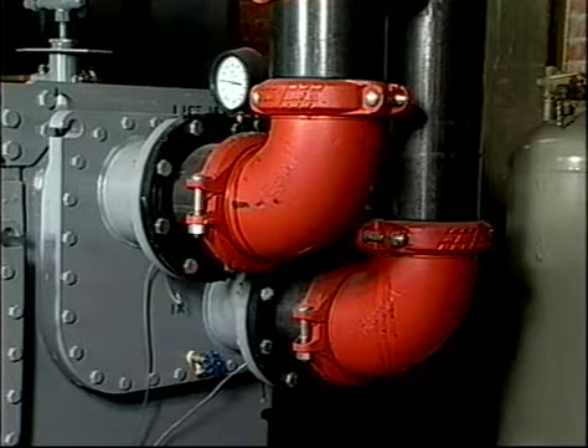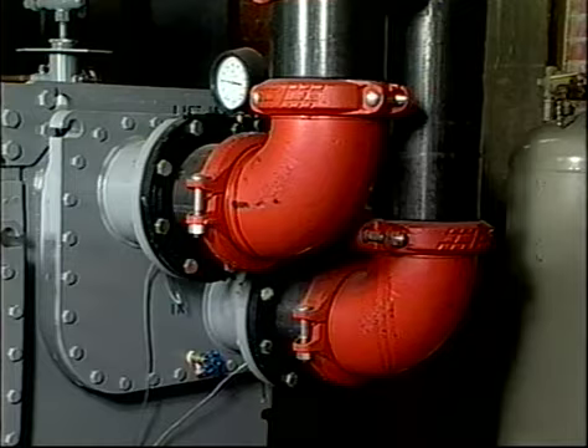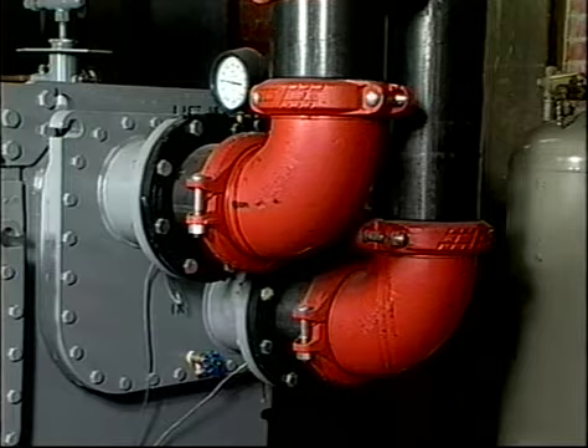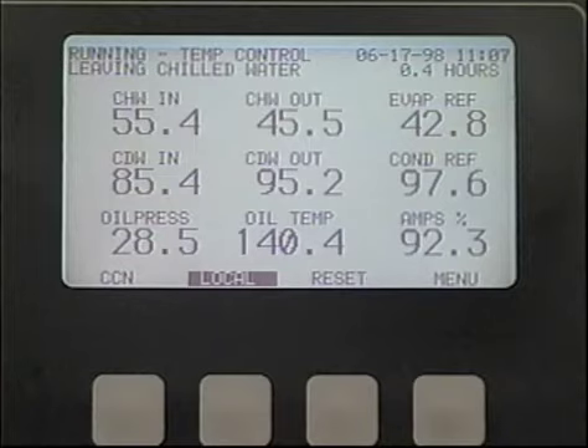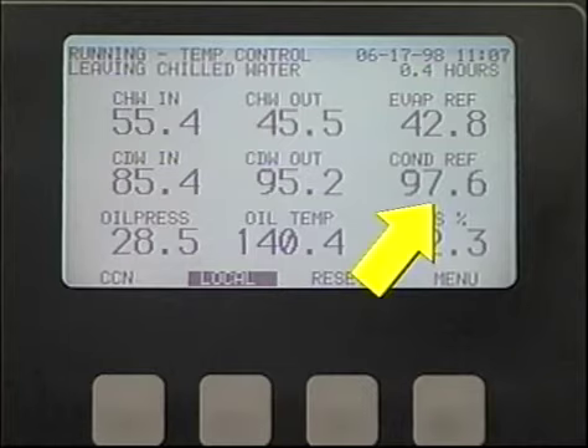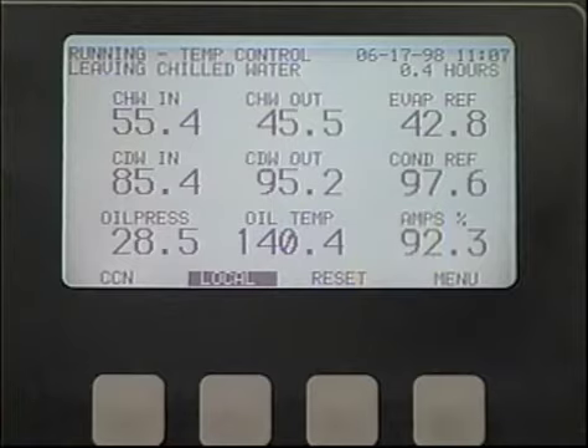Water entering the condenser should never be less than 65 degrees Fahrenheit, or there will be insufficient head pressure for proper operation. Entering condenser water should be less than design full load temperature at less than full load conditions, and the saturated temperature of the refrigerant in the condenser will range from 60 to 105 degrees Fahrenheit, depending on design conditions.